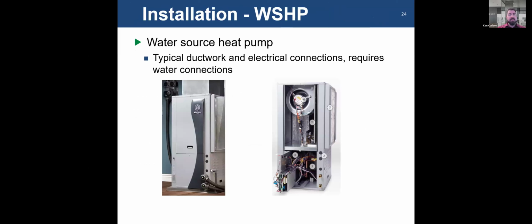As far as water source heat pumps that might be used for air distribution, right? So a geothermal system, essentially. You have your typical ductwork connections. You've got your typical electrical connections, much the same as an air handling unit. The difference is that this is a package deal, all right? Your compressor, your evaporator, condenser or coils, right? With the heat pump, it goes both ways. All part of this package.